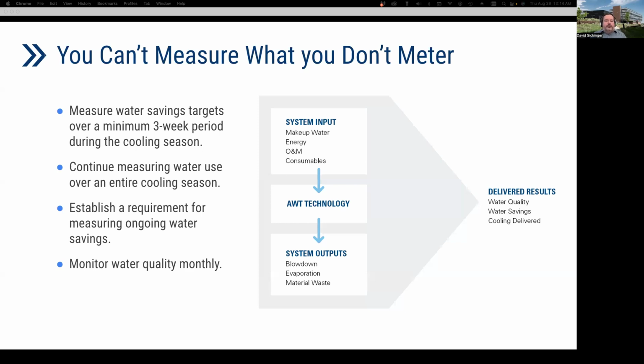The graphic on the right is showing system inputs to the AWT, so that's makeup water, some that require energy, for example, if additional pumps are required to operate the O&M, and then the system outputs that are measured. So this is blowdown, evaporation, and any material waste. And so this then is used to determine the delivered results in terms of water quality, water savings, and cooling delivered. In the report section titled Measuring AWT Performance, there is a link to a nice guide on water meter best practices. So again, you can find that in the report. So next slide.